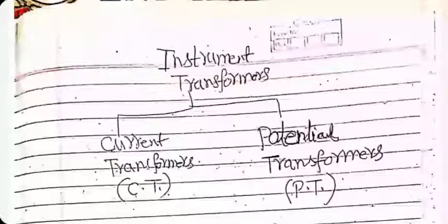So what we do is we use current transformers to reduce the unknown value by a factor, let's say 10 or 15 or something, that depends, and then measure the lower current, which can be measured using standard ammeters, and then convert the result back using the transformation ratio to the actual value. Same thing about voltage measurements also.